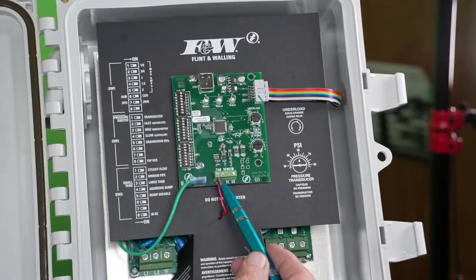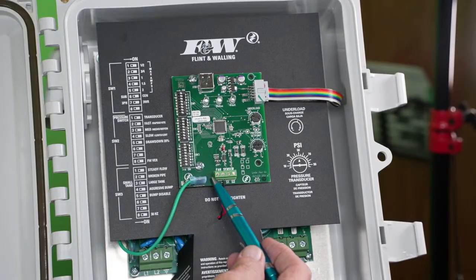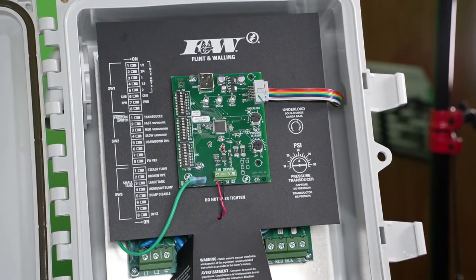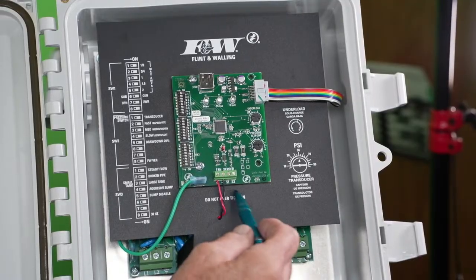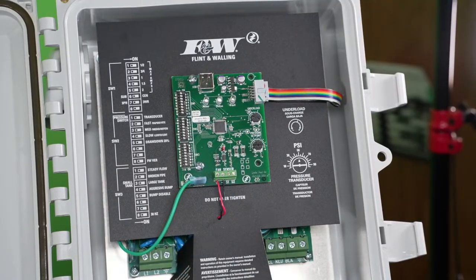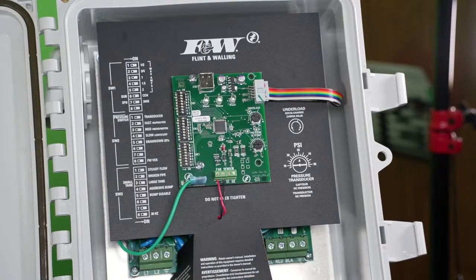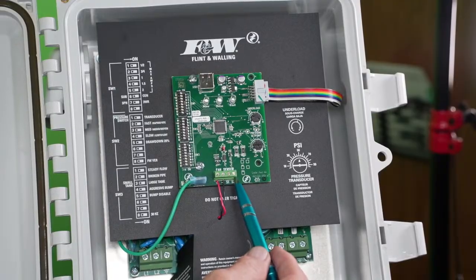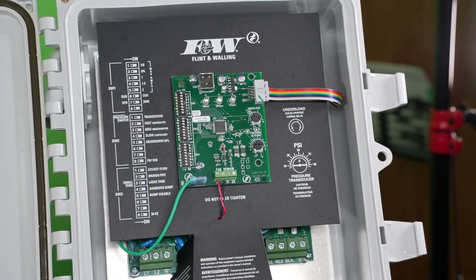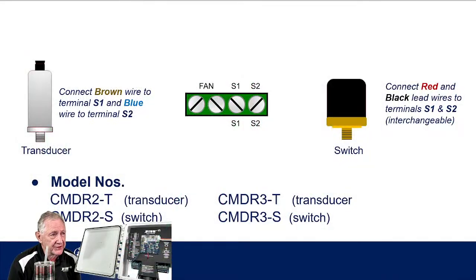Those 2 terminals on the far left-hand side, they're pre-wired. All they're doing is running down to that cooling fan that we had seen earlier. Those 2 wires run to the cooling fan. What we're going to do is wire in either one of those, the transducer or the switch. We're going to wire those in to these 2 terminals on the right-hand side. So, according to the instructions, if you're using a pressure transducer, it's going to tell you. It says you need to take that brown wire and connect it to the S1 terminal, and then take the blue wire and connect it to the S2.